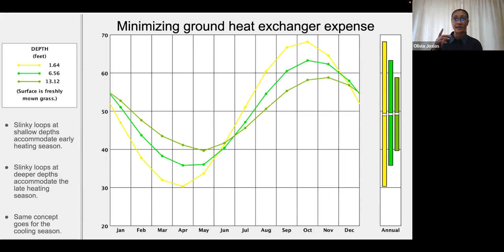We propose you go for the more cost-effective option. We intend for our suggested building designs to create self-sufficient heating and cooling within themselves, allowing the slinky loops to restore and recharge on the daily and prolonging its functionality throughout these different seasons. If you invest in the slinky loops now, you are not limited to future additions, meaning if you find that more support is required, there's always the option to add some boreholes down the line to improve the heating and cooling balance. To the right is our conceptual design of a hybrid method of systems that includes both the vertical and horizontal techniques. This shows how multiple geothermal systems can work together. If you'd like to take a look at that.